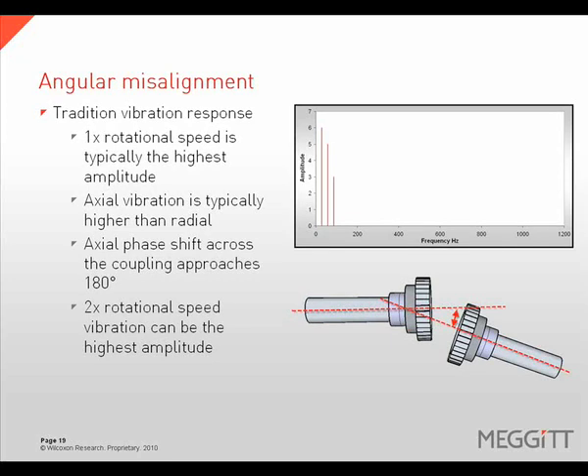Angular misalignment is characterized as having higher 1x rotational speed vibration, with the highest amplitudes often in the axial direction. The phase shift across the coupling should occur in the axial direction, and the analyst must consider the orientation of the transducer when collecting axial phase readings to obtain accurate measurements. While 1x is the most common response to angular misalignment, it is not uncommon to find 2x rotational speed vibration being the highest in amplitude, making it difficult to distinguish between offset and angular misalignment based on spectral data alone.